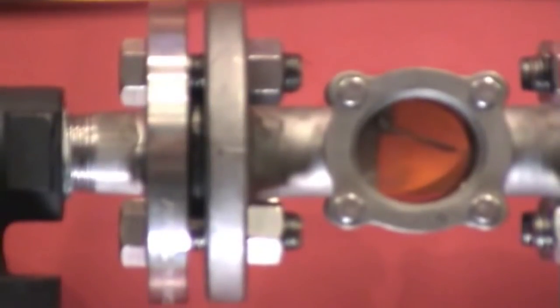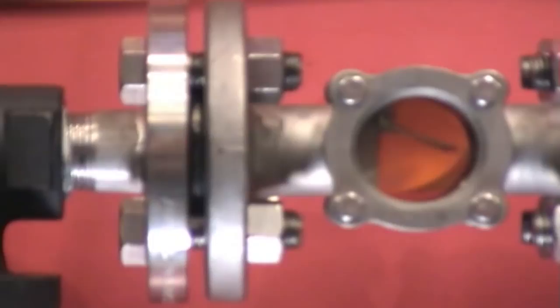Here we see the discharge as the little flapper shows that we do have flow going through it. You can see that all condensate is gone and we now have clean dry steam to be fed to equipment.